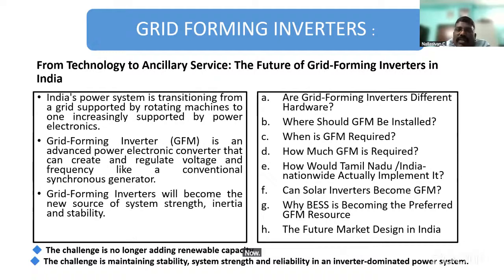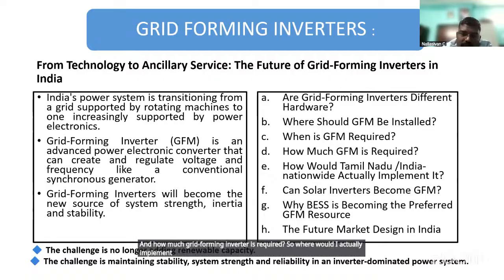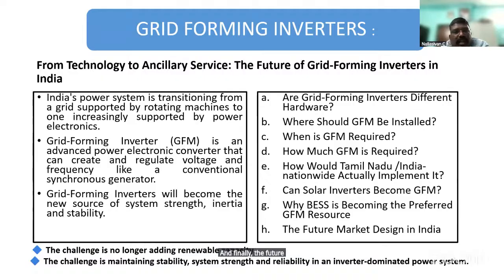How are these grid forming inverters different in terms of hardware? Where should grid forming inverters be installed? When are they required, and how much is required? Where would I actually implement it, either in Tamil Nadu or in India? How do existing solar inverters become grid forming? How do battery energy storage systems become the preferred grid forming sources? And finally, the future market designs in India, from technology to ancillary services, as I have highlighted.